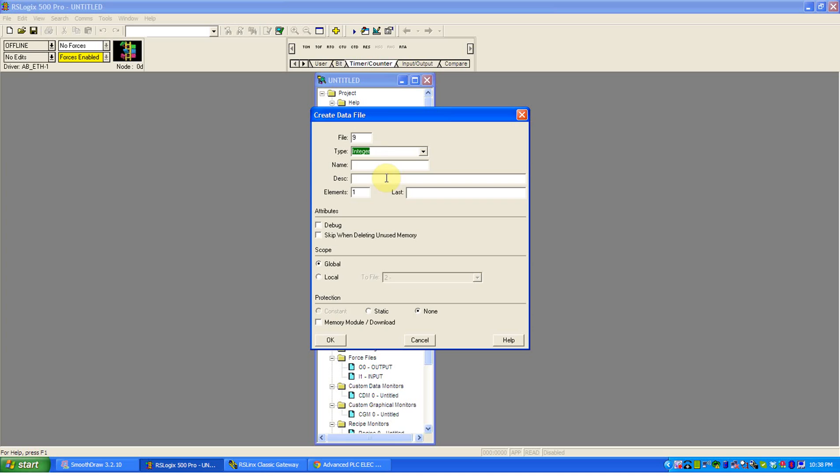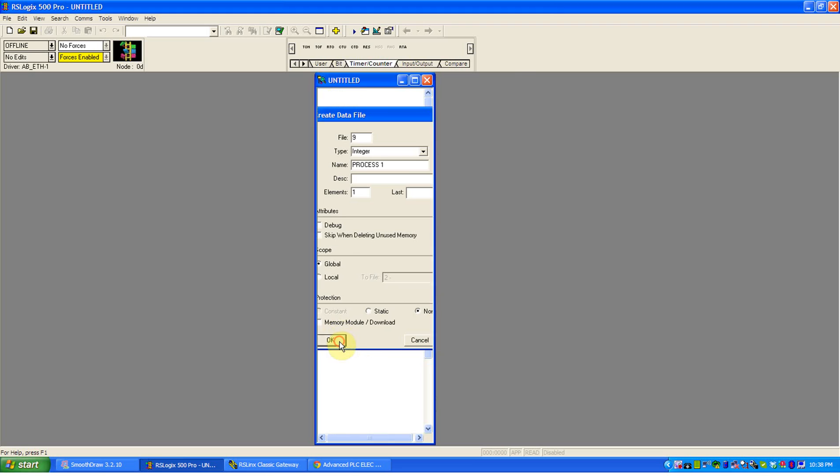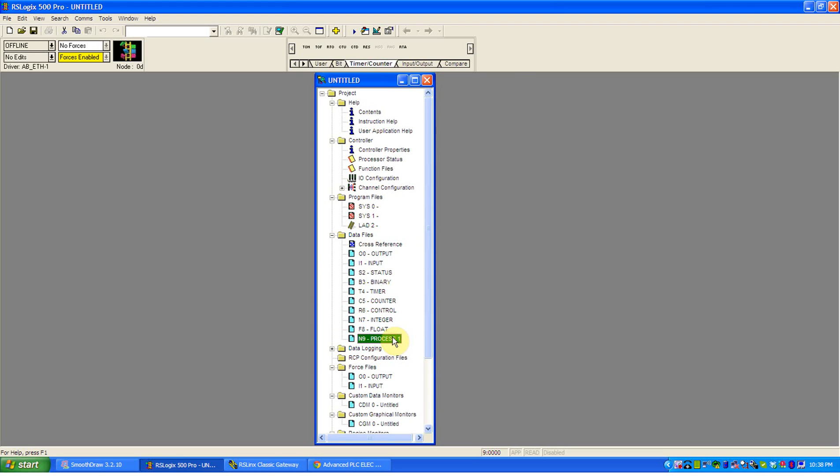But for example, I could say integer, I could give it a name, process one, a description if I wanted, how many elements, what's its size, global meaning it's available everywhere, local meaning it's only available in a particular subroutine like ladder two, ladder three, ladder four. Again, see the program control video to better understand that idea. We'll leave it as global. And when I hit it, you'll see that process one shows up as N9.